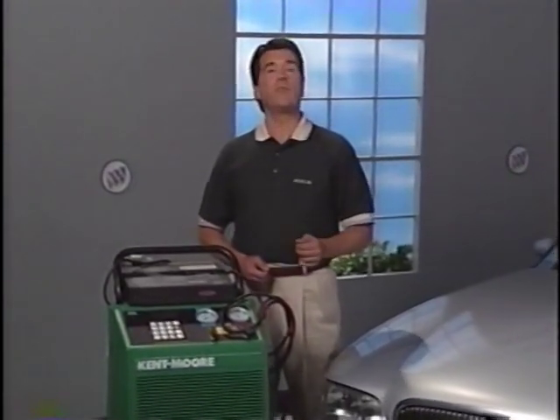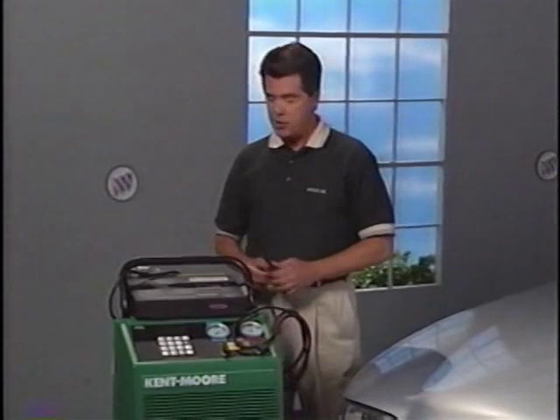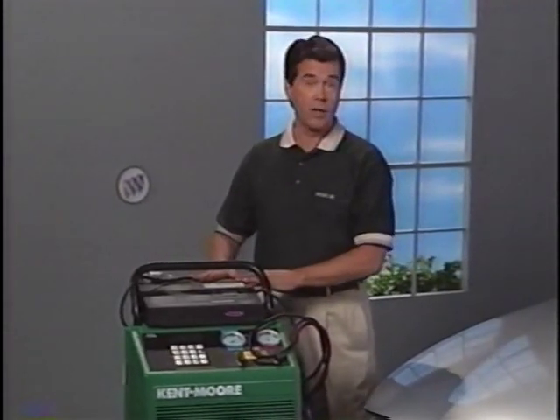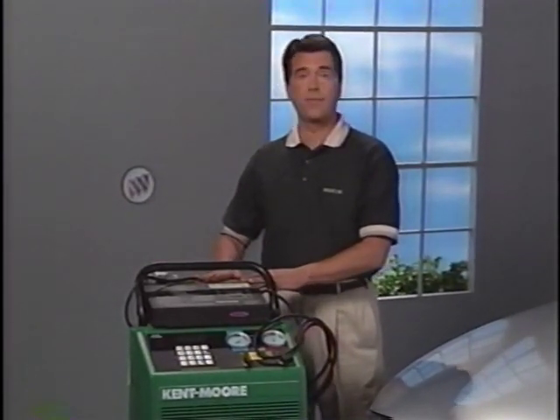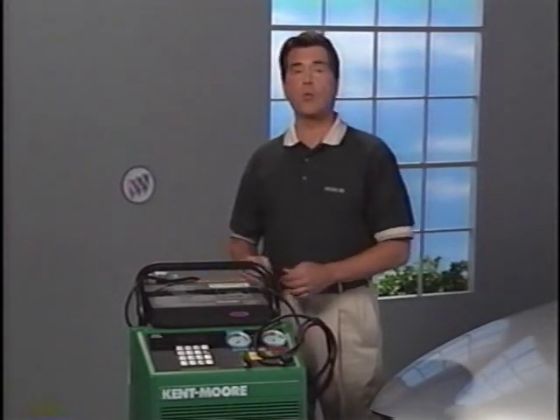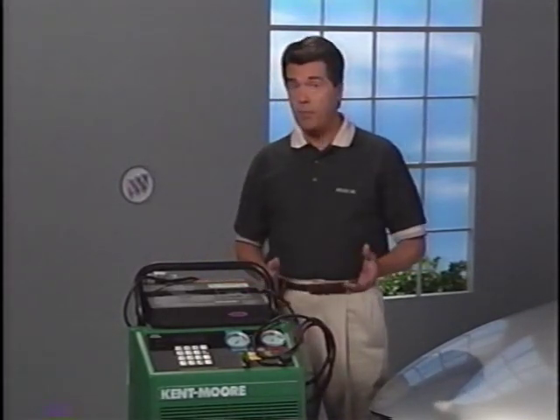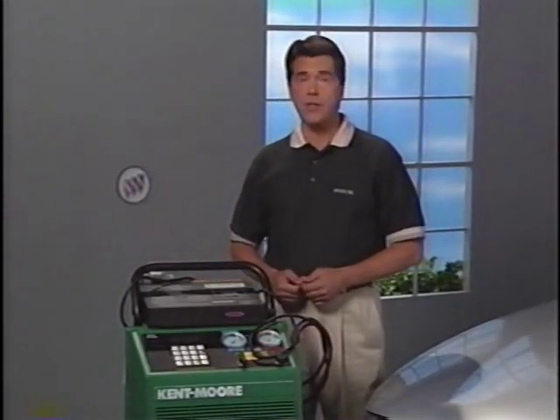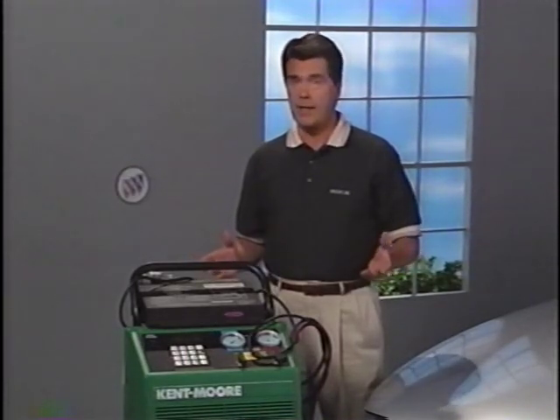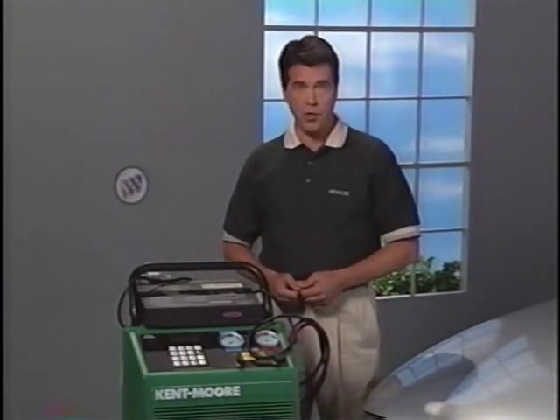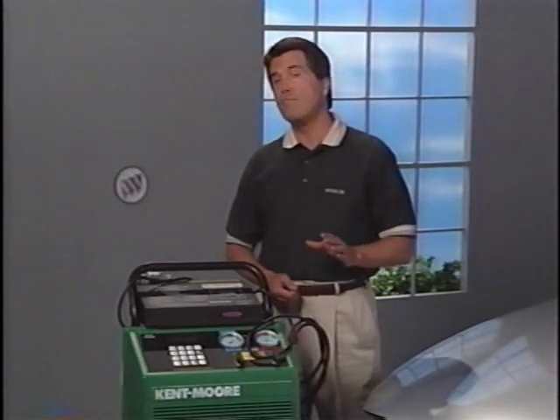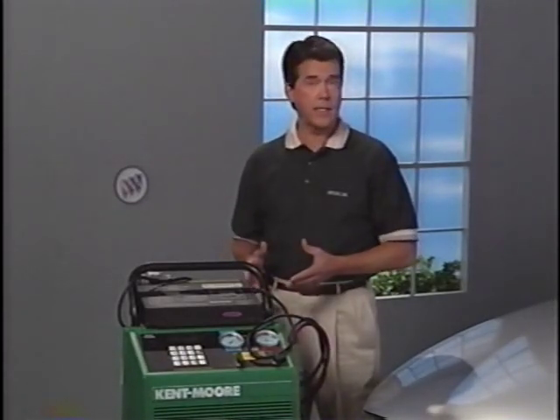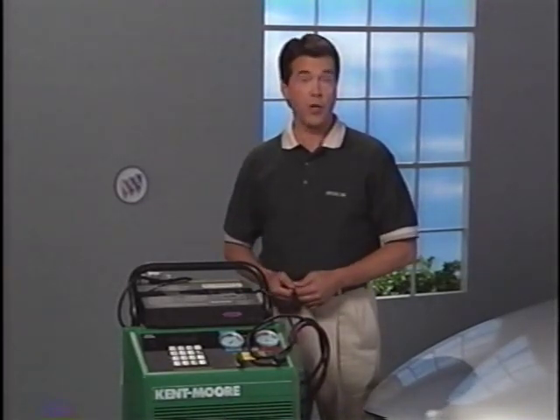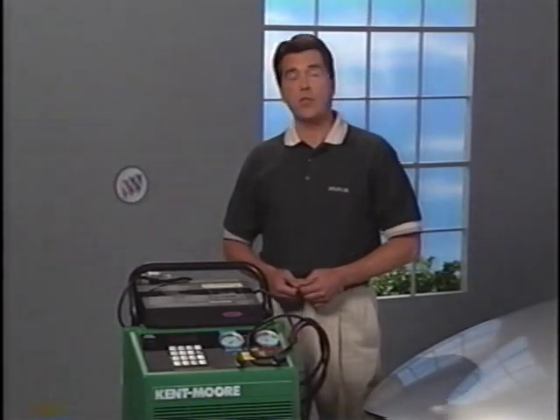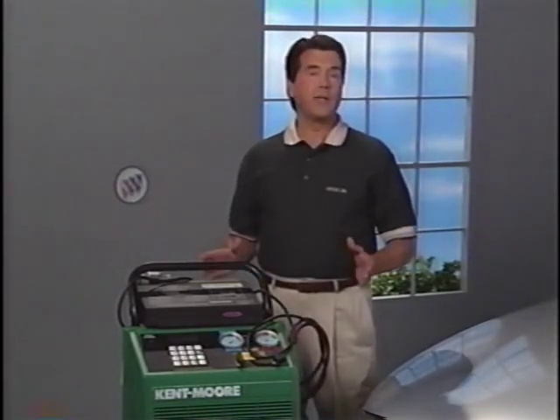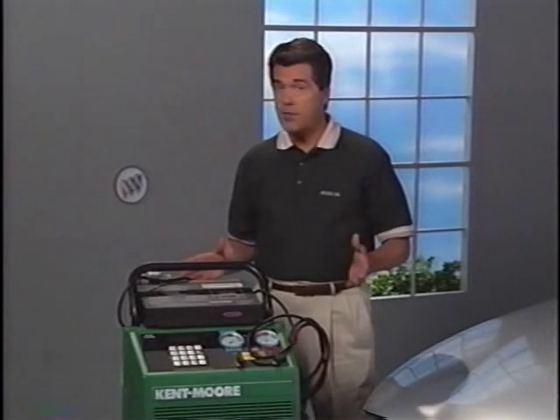We're told a number of PureGuard 2 units have been damaged as a result of being flooded with oil and liquid refrigerant. This flooding can be caused by incorrect service procedures or by unique AC service conditions that occasionally arise. Then I'll show you some new materials and equipment for dealing with the buildup of mold and mildew in the AC system and the odors associated with that. Also, I'll be discussing some AC-related conditions that have recently arisen in the field.